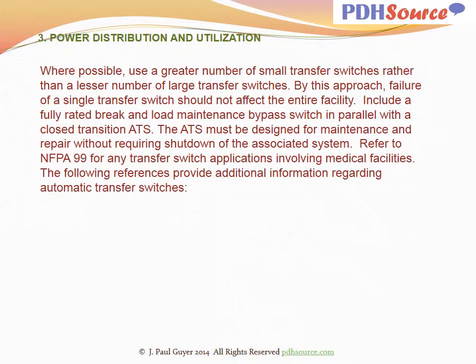Where possible, use a greater number of small transfer switches rather than a lesser number of large transfer switches. By this approach, failure of a single transfer switch should not affect the entire facility. Include a fully rated break and load maintenance bypass switch in parallel with the closed transition ATS. The ATS shall be designed for maintenance and repair without requiring shutdown of the associated system. Refer to NFPA 99 for any transfer switch applications involving medical facilities.